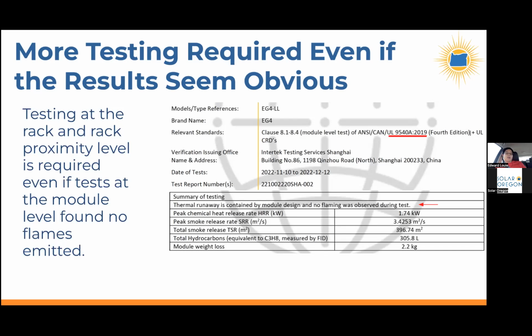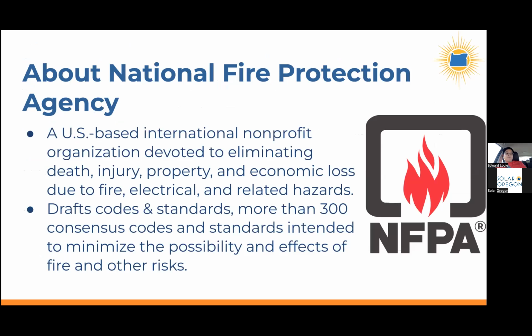So if we were to stack 6 of them in the rack, theoretically, then with the findings from this burning of one module, you would think that the other 5 modules in the rack would be fine. Well, that's not good enough. The UL 9540A test is such that you would need to do the same test with a rack full of 6 batteries, even though with the findings of one, it seems to be pretty obvious what would happen when you stick adjacent batteries to the system. And so those are the test procedures at the cell level, the module level, and then also if you were to put them in racks, there are different UL test requirements.